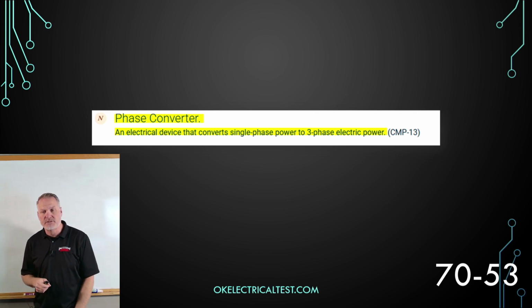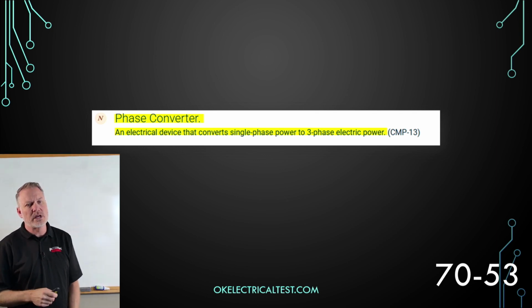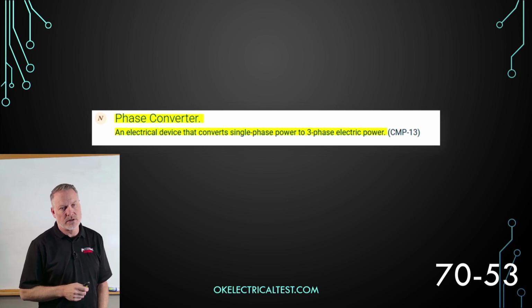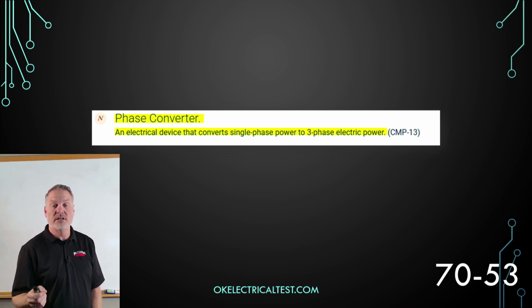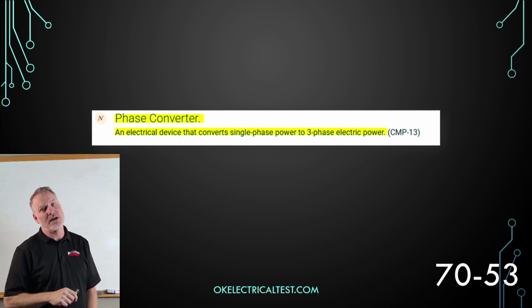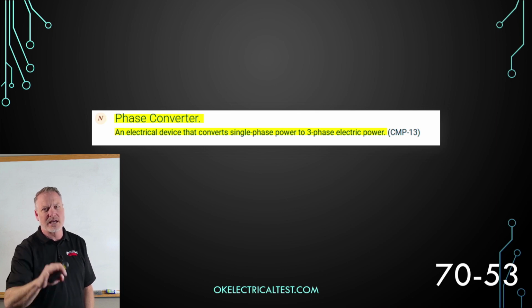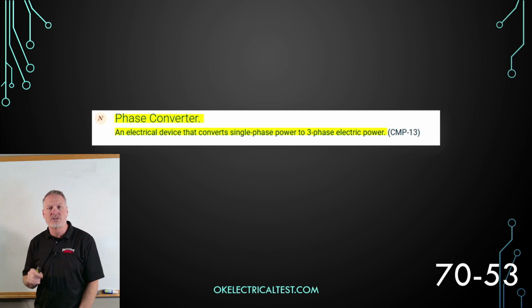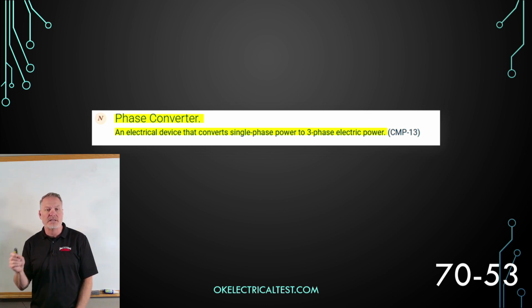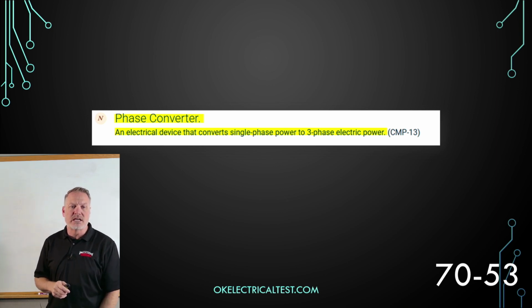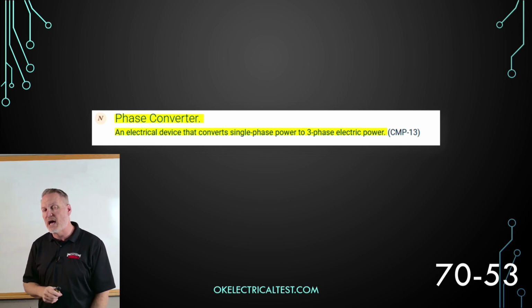Letter P, page 53. Page 53, letter P, we've got a phase converter. And again, this is a new definition in this article, but it's not a new definition for the code. In previous codes, this was back in our phase converter article. I believe that's article 455, something like that. And phase converters, that definition was back there. Now it's here in article 100. So phase converter, that's an electrical device that converts single phase power to three-phase power.